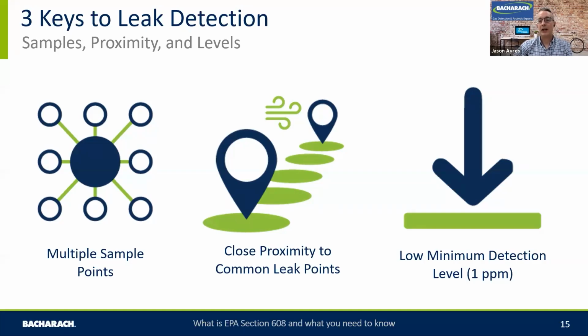And finally, detecting it at a lower ppm level. If you're detecting it in the hundreds of ppm, you're going to be at a point where you've got a significant refrigerant loss, and it's also going to start impacting the operation of the system. Having the right technology and a low level leak detection level all the way down to 1 ppm allows you to transform your view of leaks. Get to them sooner, get to them closer, and keep as much of that refrigerant as possible contained within the system.